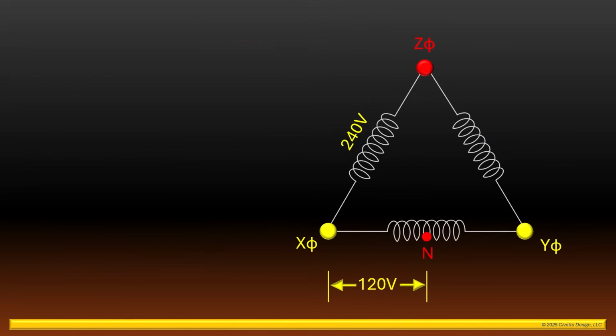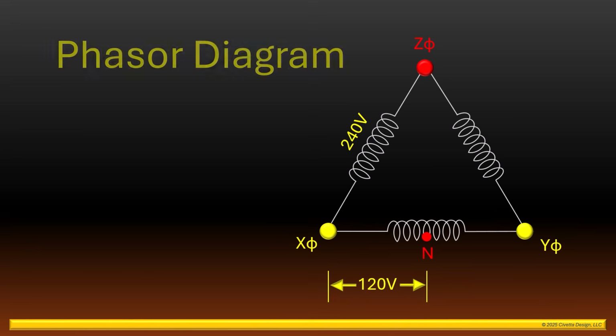These diagrams that we've been looking at aren't just for the physical connections in the transformer. These are also called phasor diagrams. Engineers use phasor diagrams to determine different voltages in a variety of transformer configurations. In this particular configuration, we want to know what voltage is created when we connect the Z phase to the neutral.